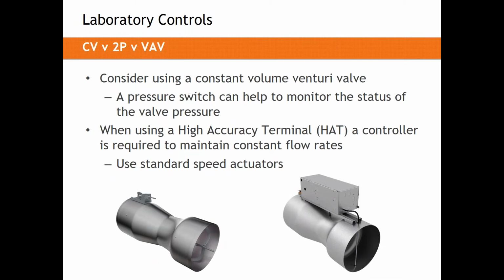My recommendation is you should always strive to use a constant volume Venturi valve. That's a bit of a blanket statement, but I do stand behind it. If you have true constant volume and you know it's going to maybe change once in its lifetime, meaning 5 years down the road, you might change the flow by 100 or 200 CFM, for example, try to use a constant volume Venturi valve. It's the least expensive, the least complex, and the easiest to set up. The maintenance is the lowest, and it will still provide you stable and accurate control all of the time. This is the best solution for a lot of applications.